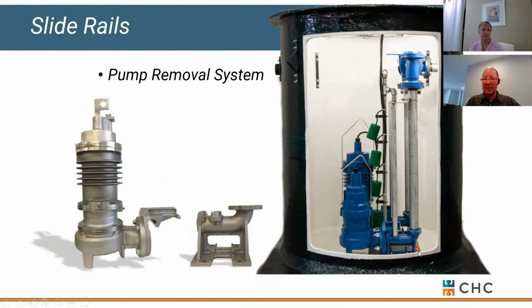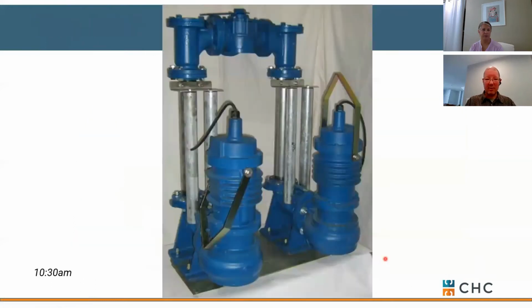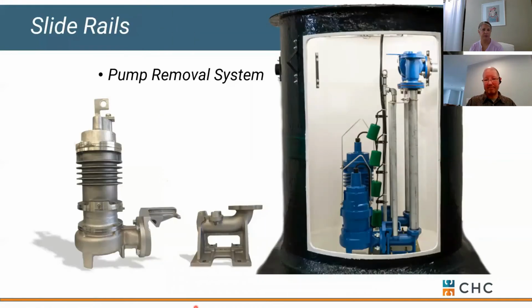Typically what you've got is what we call a guide plate that sits at the bottom of our basin. It helps to center our removal elbows. So that's all this plate is. It's got studs on it, so your elbows mount to that. And it happens to be centered with the cover that's on the top of our basin. So we've got a guide base at the bottom, and then we've got these things we call removal elbows, like shown right here. And these simply get anchored.